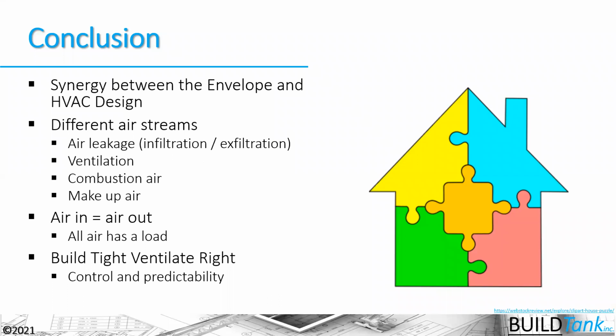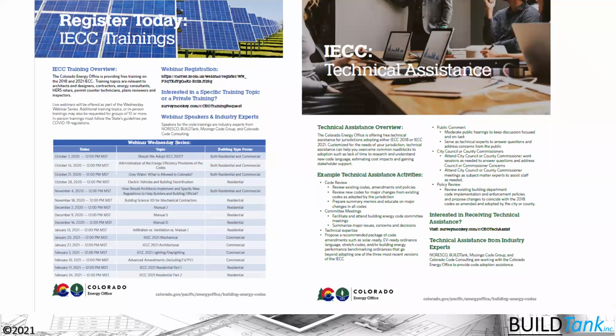The air leakage is talked about in terms of infiltration and exfiltration. Ventilation is the air that you're bringing in for the houses, because when we build our houses tight, we need to ensure that there's fresh air and background moisture control. But we also have combustion air and makeup air that we need to take into account. Any air that's coming into the house is leaving the house, so that notion of air in equals air out. And all that air is part of the load, the Manual J load of that house. So we want to build our houses tight, ventilate them right, gain control and predictability of the airflow in their houses, because air is a transport mechanism. It's transporting heat, it's transporting pollutants, it's transporting moisture around our houses. And we need that control and predictability to have an efficient, a durable, a comfortable, and a safe house for our occupants. So thanks so much for joining us today.